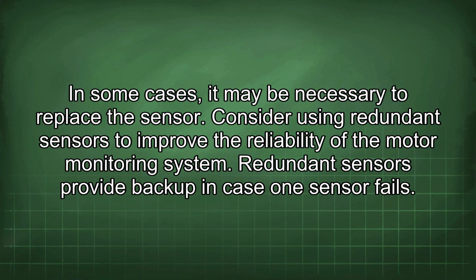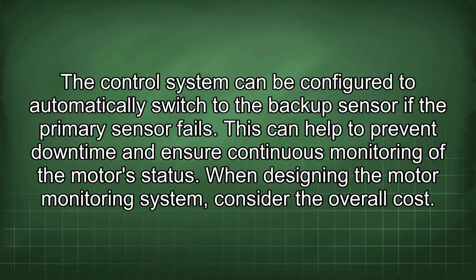Consider using redundant sensors to improve the reliability of the motor monitoring system. Redundant sensors provide backup in case one sensor fails. The control system can be configured to automatically switch to the backup sensor if the primary sensor fails. This can help to prevent downtime and ensure continuous monitoring of the motor's status.